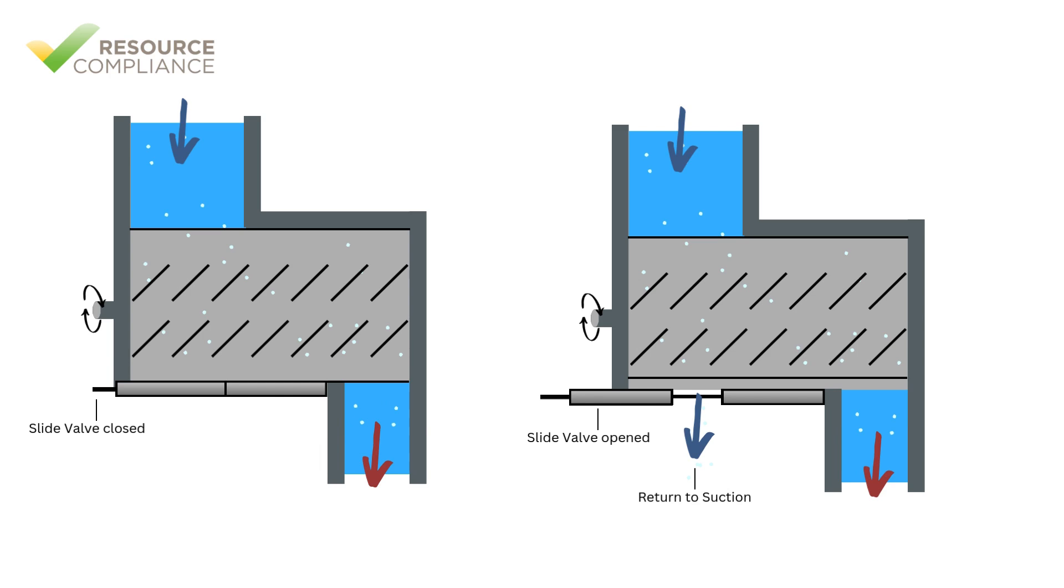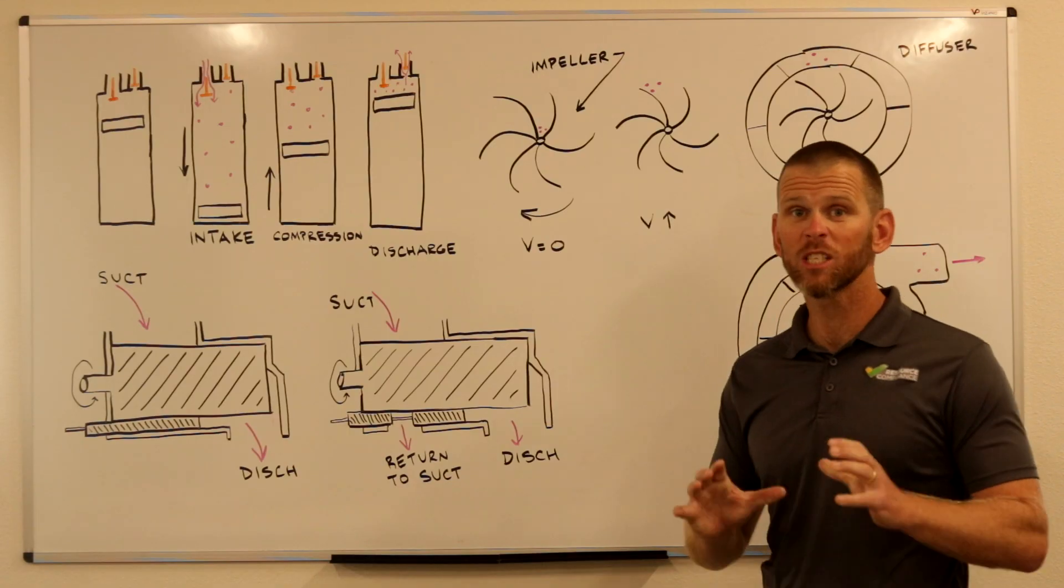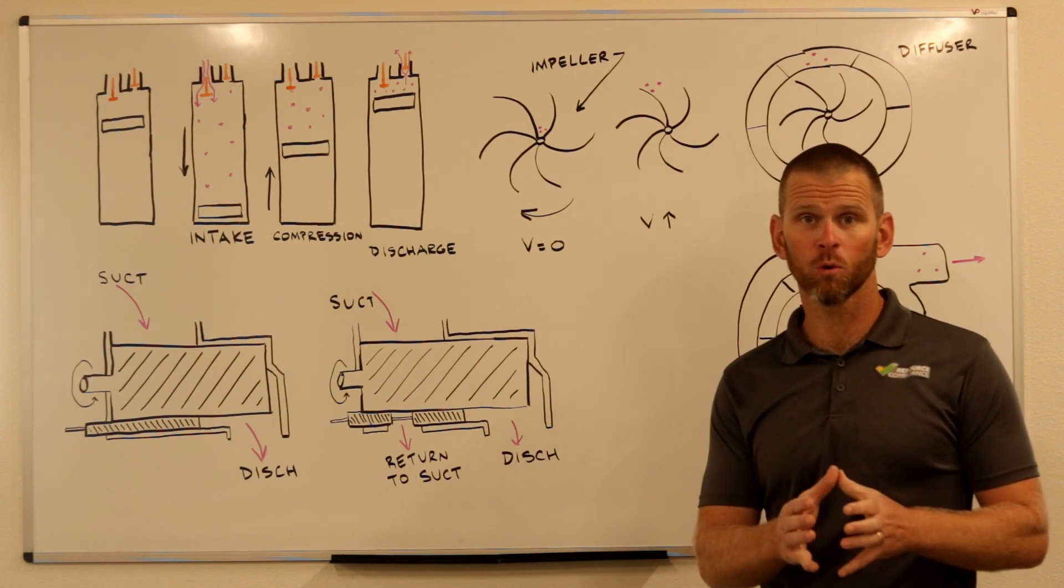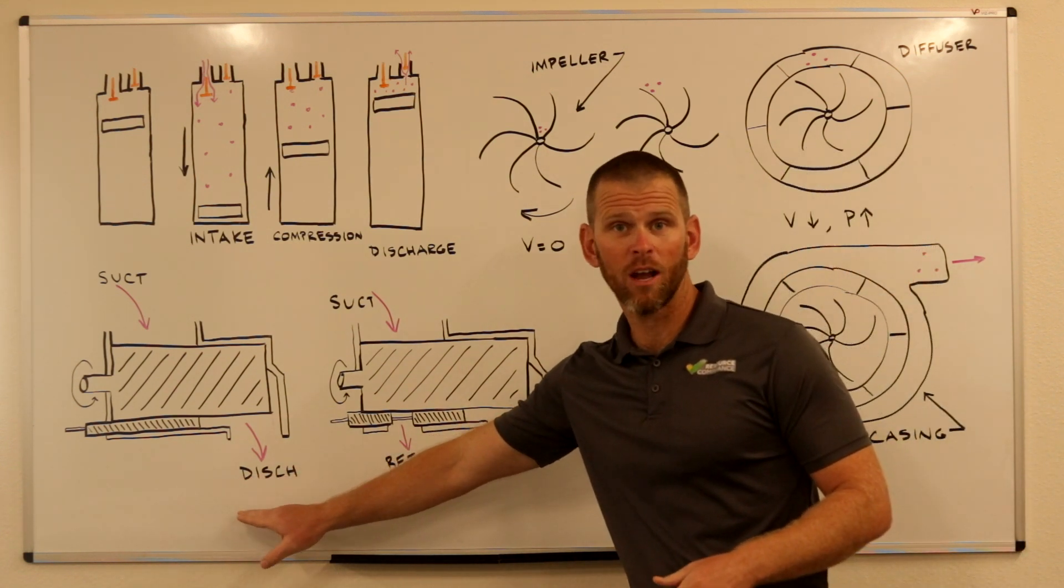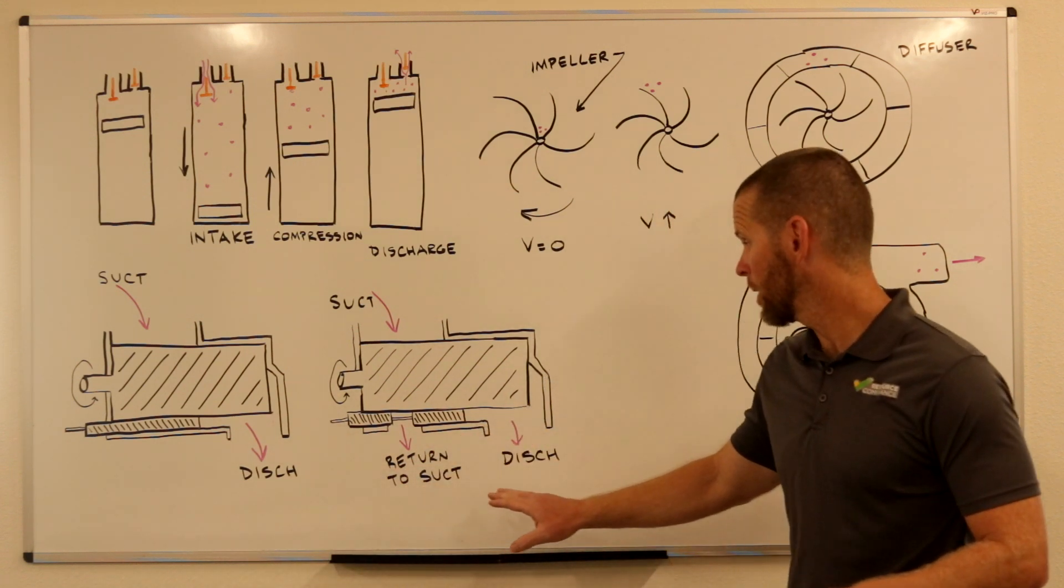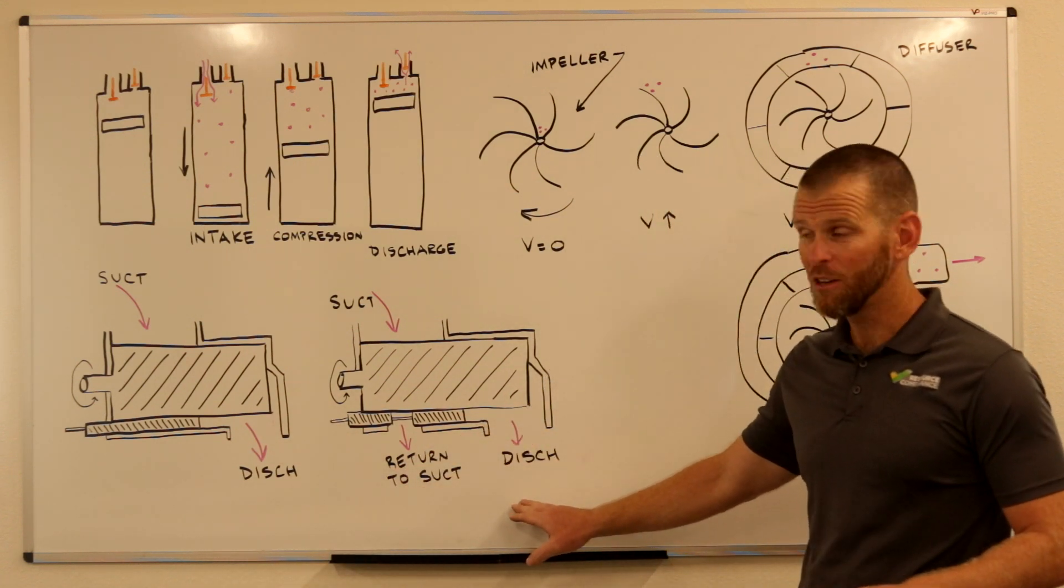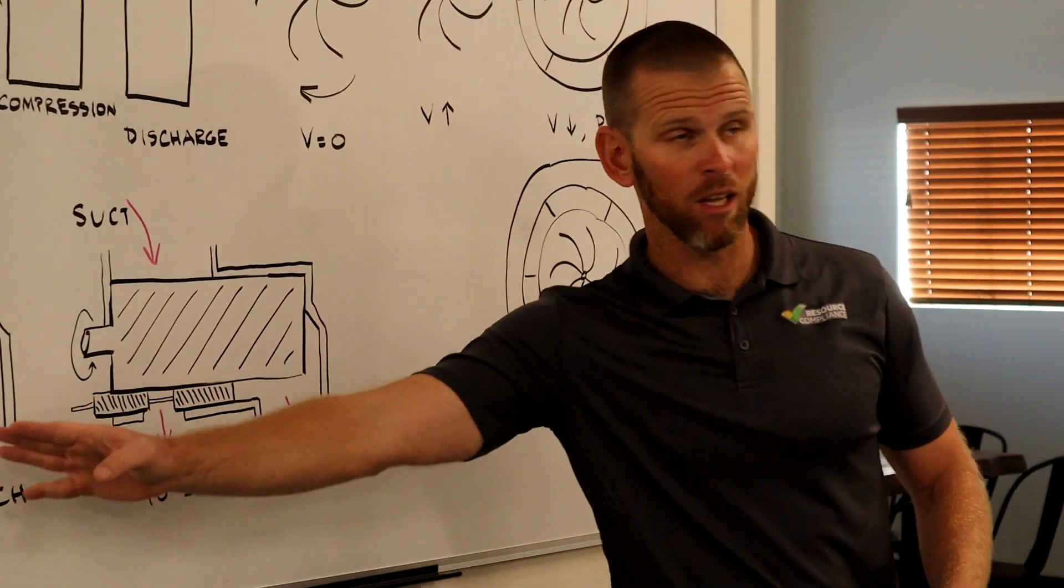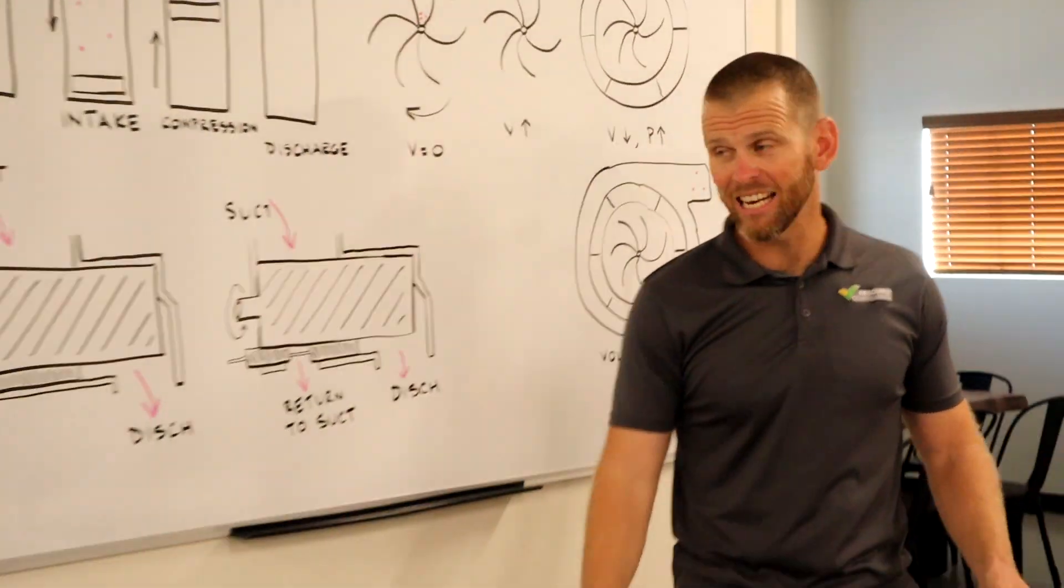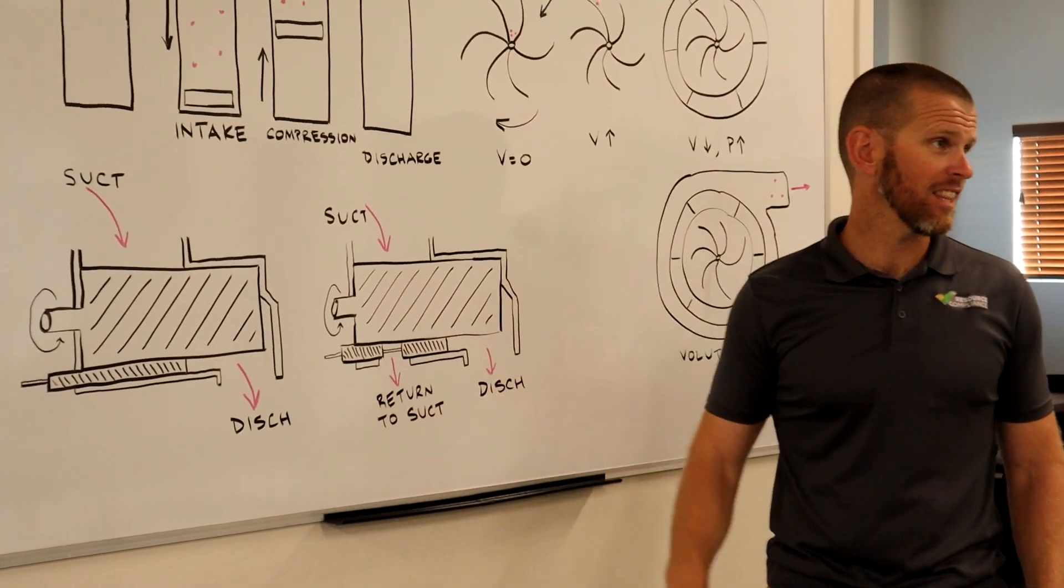Slide valves allow screw compressors a continuous range of unloading, typically from 100% down to 10% of their full capacity. So to explain capacity control in a screw compressor, I've modified the diagram we use to talk about variable volume just slightly.